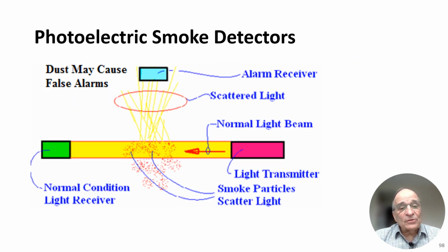And there are photoelectric smoke detectors, and this would have a light source, which is powered, and a receiver. It would have a receiver that's at 90 degrees. Now, this receiver would not receive any light unless particles of smoke were to come in here and reflect that light. Now, the negative part of this is dust or debris; any kind of a dusty environment could certainly also trigger this type of smoke detector. But the light that is received by this sensor only occurs when some kind of a reflective material comes into this area, and that reflective material would be smoke. So smoke does reflect a certain amount of light received by this sensor, and the smoke alarm goes off.